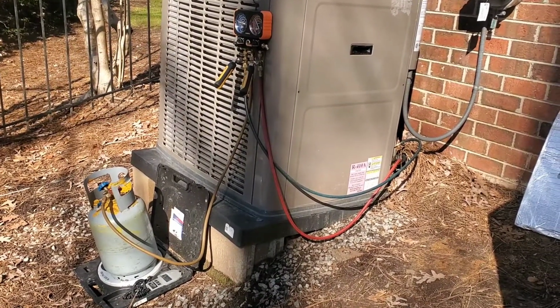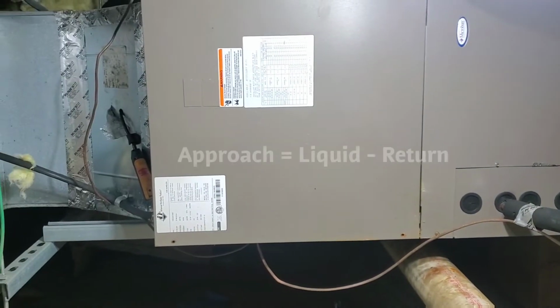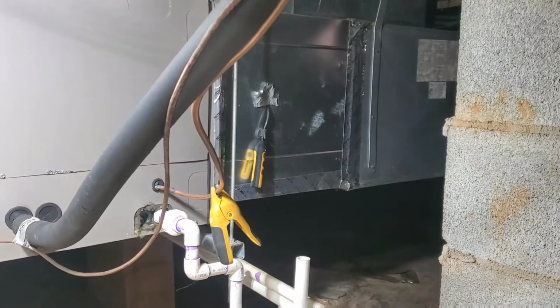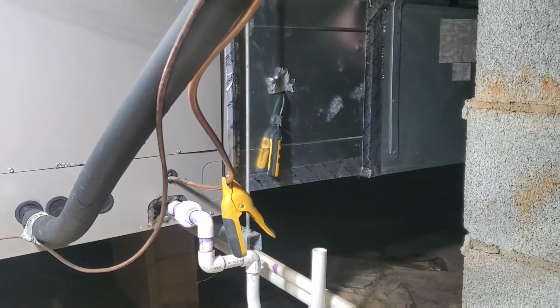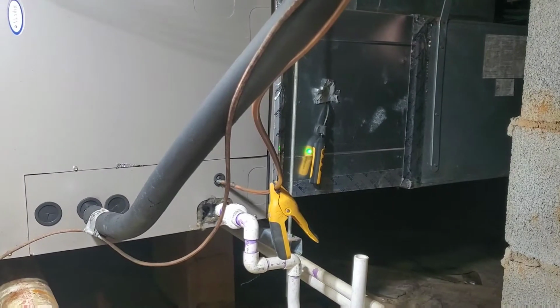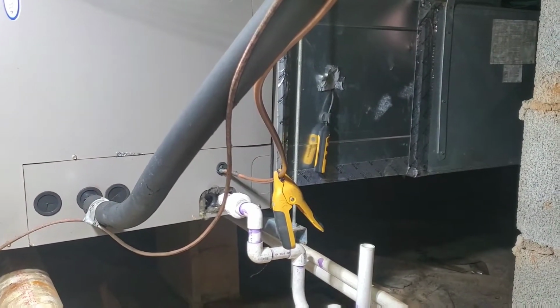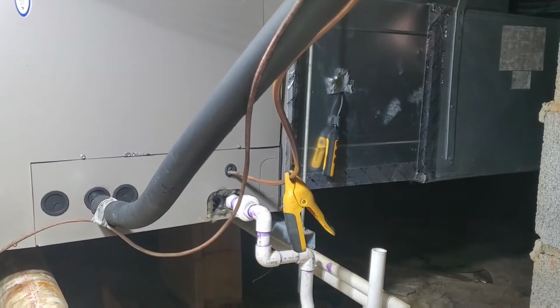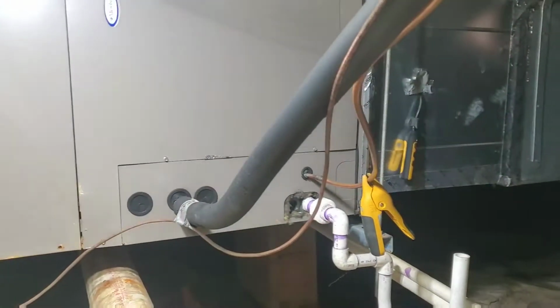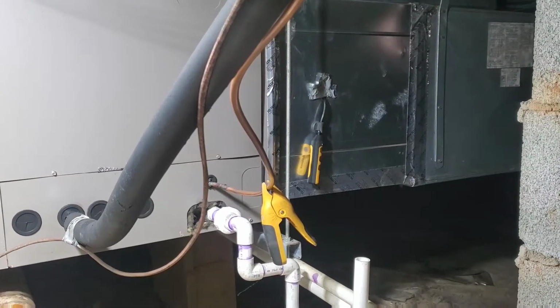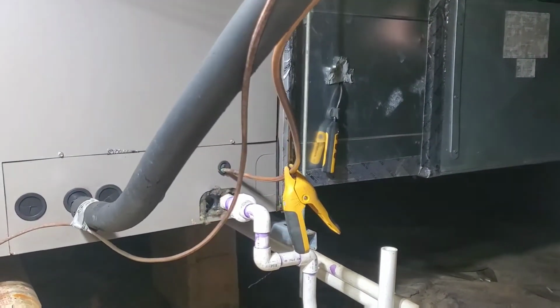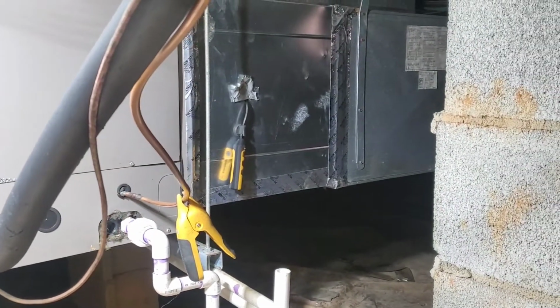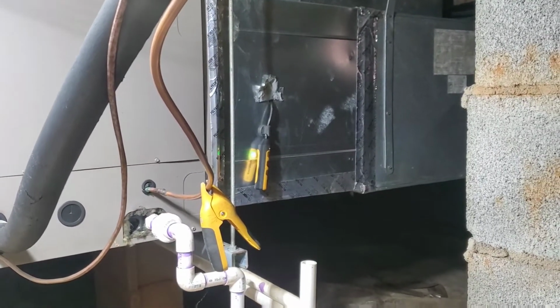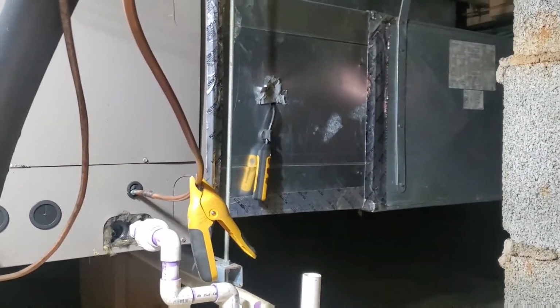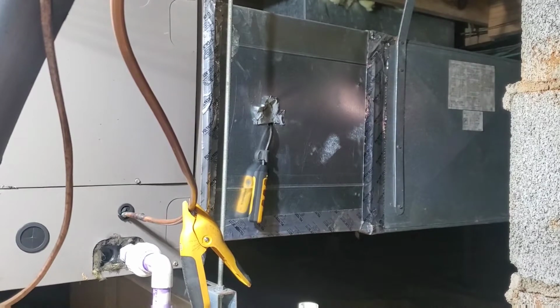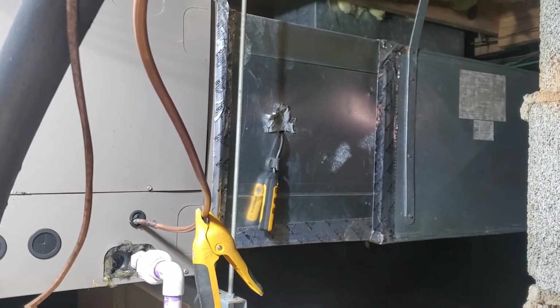And I'll explain why. So as a reminder, approach temperature is the difference between your return air temperature and your liquid line temperature when you're talking about a heat pump in heating mode. Now in cooling mode, you would measure your liquid outside and you would take your outdoor temperature. But in heating mode, because your indoor coil becomes your condenser, approach temperature is measured by subtracting your liquid temperature coming out of your indoor coil from your return air temperature. Typical approach temperature is going to be somewhere between 3 and 17 degrees typically in heating mode. But you should always have some kind of approach temperature.